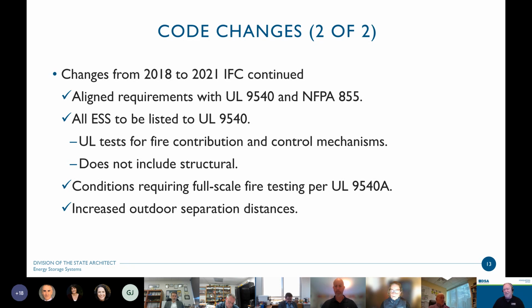When we talk about UL 9540, what UL tests for and what that listing encompasses is the fire contribution and the control mechanisms that are associated with these energy storage systems. The 9540 listing does not test for or include any review of the structural provisions that these pieces of equipment are required to comply with per Section 1207. It does contain conditions requiring full-scale fire testing per UL 9540A under certain conditions, and it did increase the outdoor separation distances.